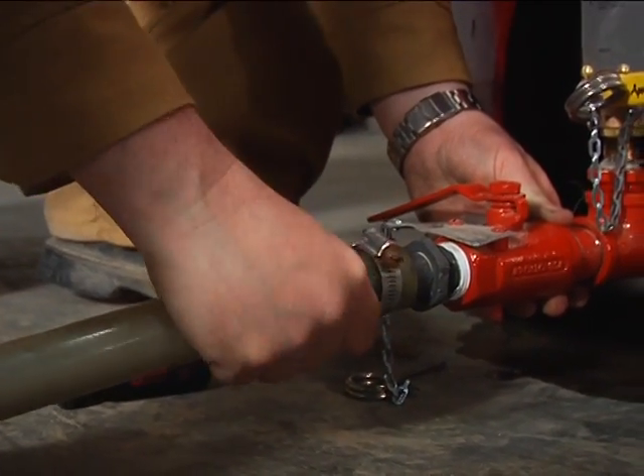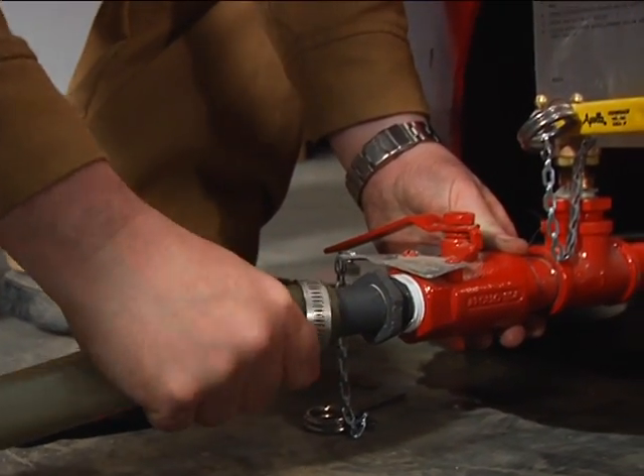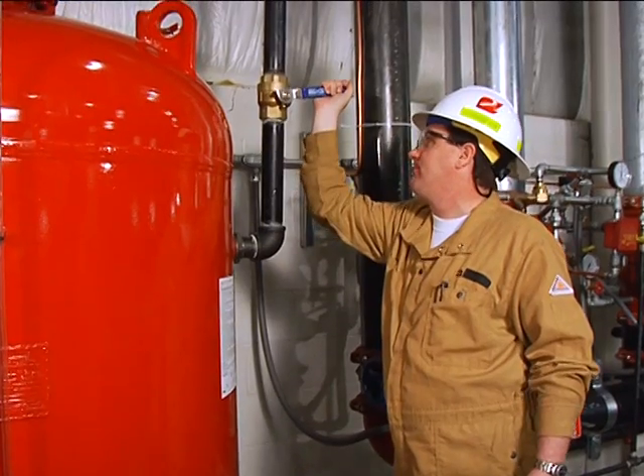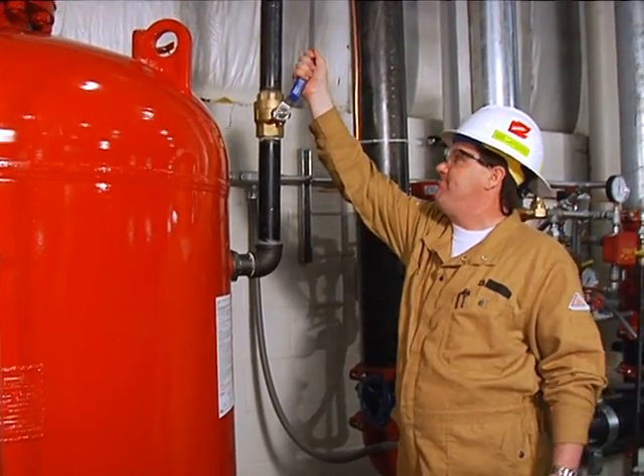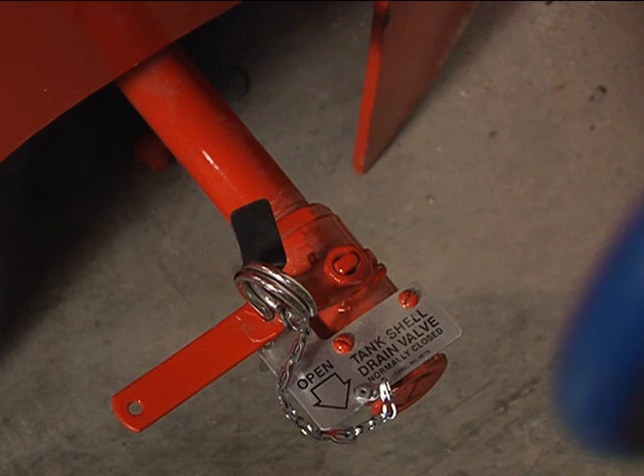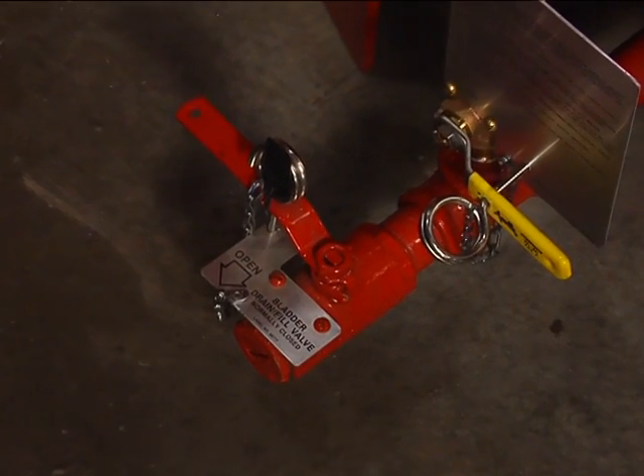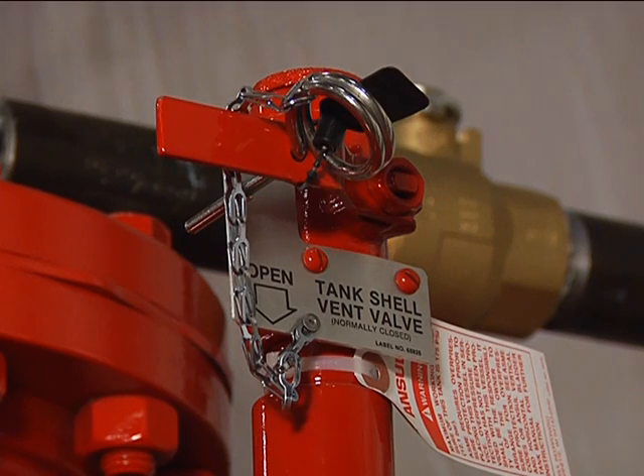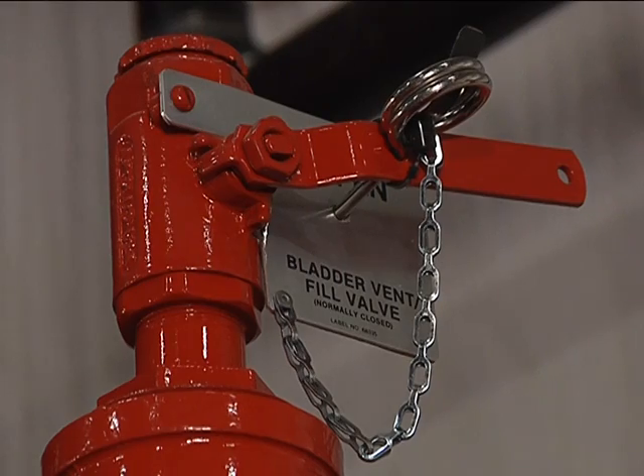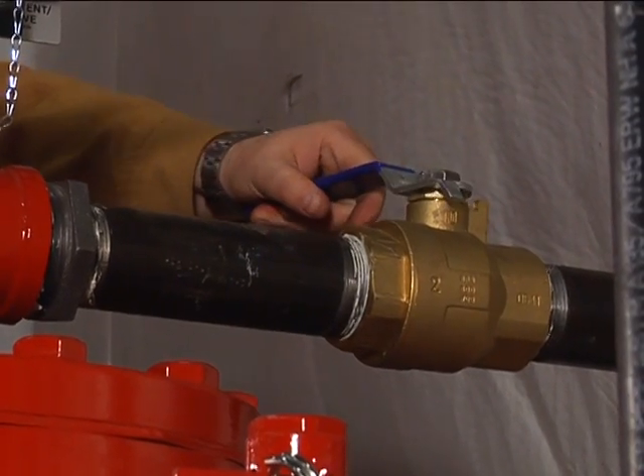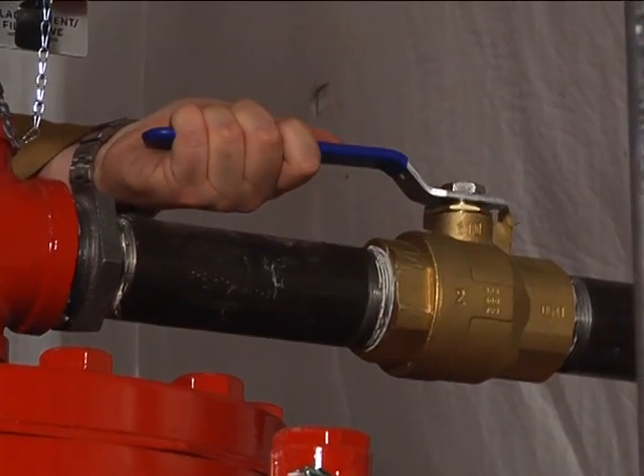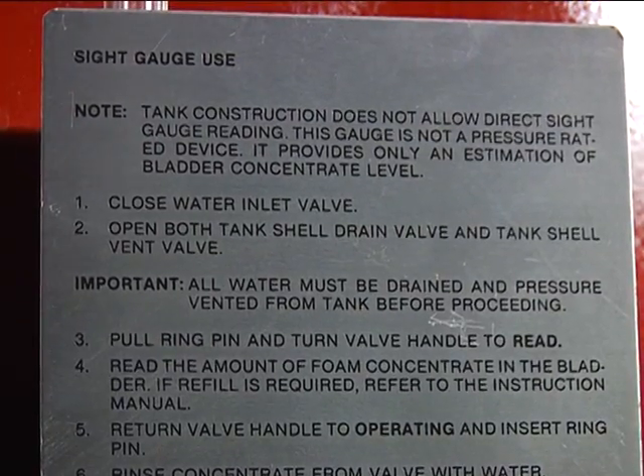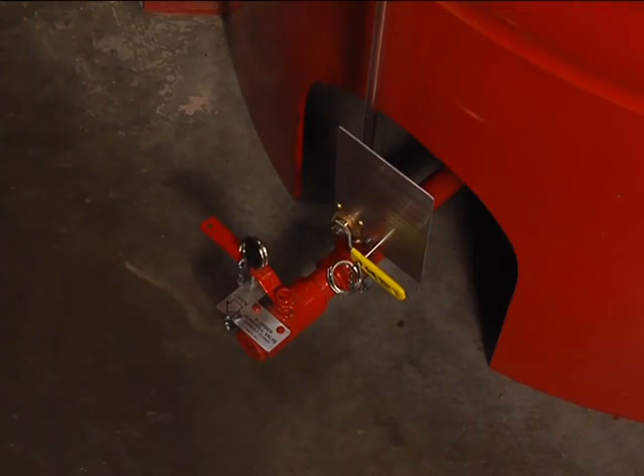Now return the bladder tank valve handles to the following operating positions: water inlet valve, open; tank shell drain valve, closed; bladder drain fill valve, closed; tank shell vent valve, closed; bladder vent fill valve, closed; concentrate isolation valve, normal operating position. If provided, sight gauge valve, operating.